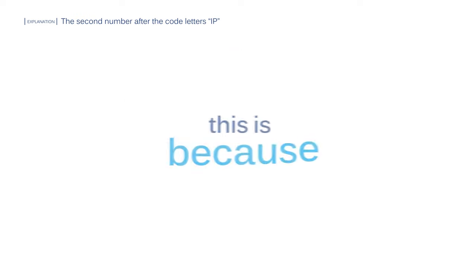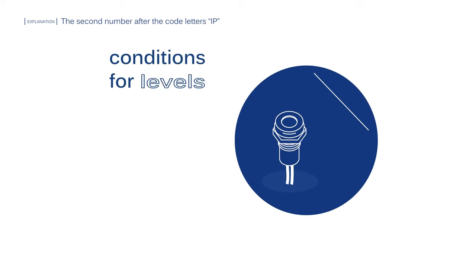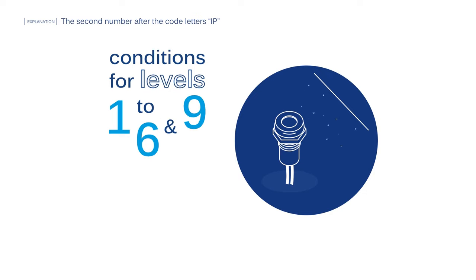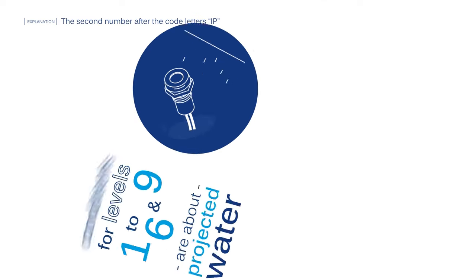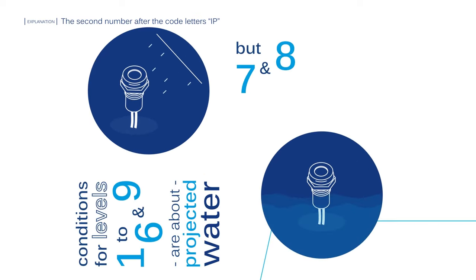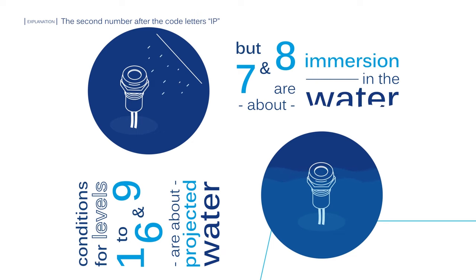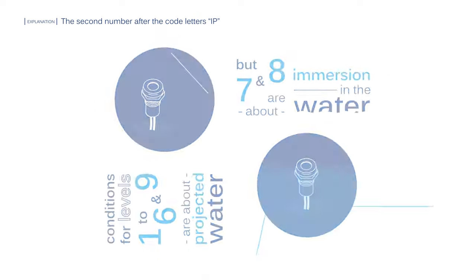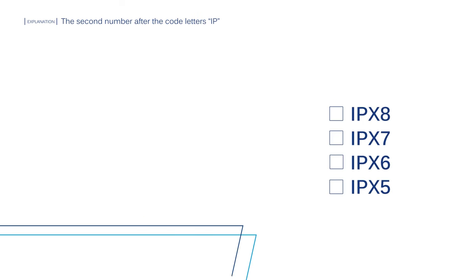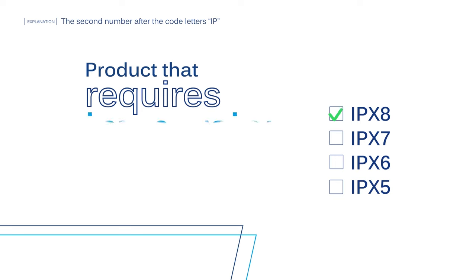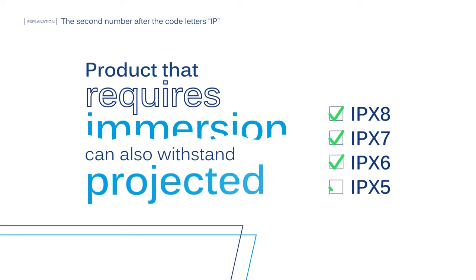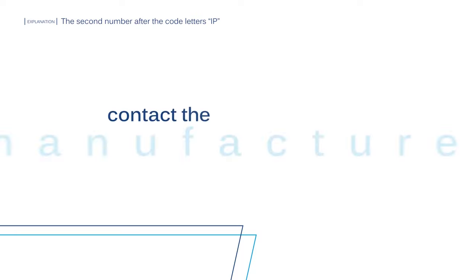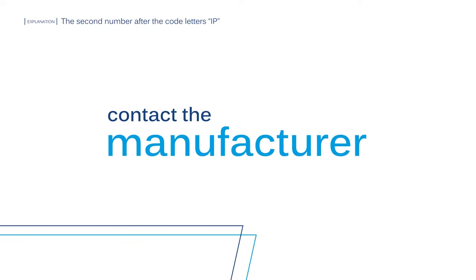This is because the conditions for levels 1 to 6 and 9 are about projected water, but 7 and 8 are about immersion in the water. However, it can be that a product with a rating that requires immersion can also withstand the levels with projected water, and vice versa. You would have to contact the manufacturer to be 100% sure.